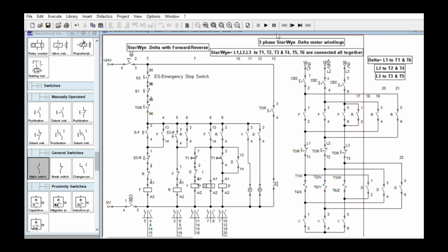Okay, in power circuit, this is drawn with heavy lines, and you can label them 1, 3, 5, 2, 4, 6 in IEC, ISO standard. Odd numbers input, even numbers output of the power switch, power circuit breakers, or power switches, or power contactors. 135246, 135246. And that is in the actual contactor. There is label there.